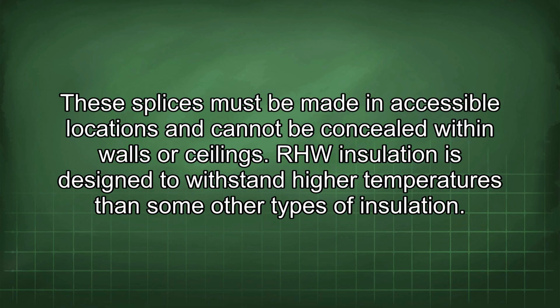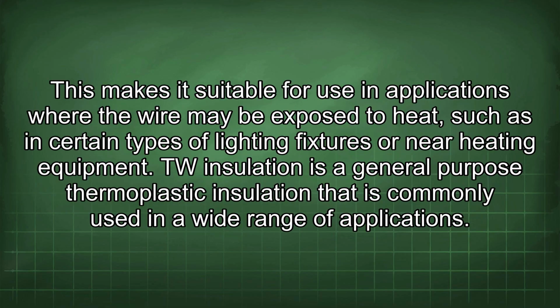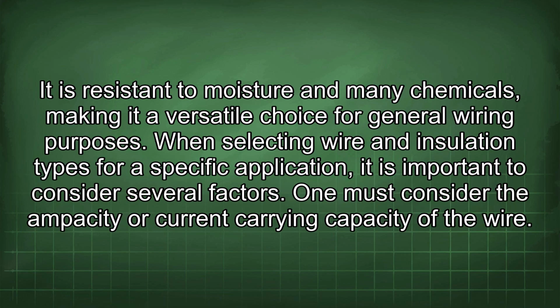RHW insulation is designed to withstand higher temperatures than some other types of insulation. This makes it suitable for use in applications where the wire may be exposed to heat, such as in certain types of lighting fixtures or near heating equipment. TW insulation is a general-purpose thermoplastic insulation that is commonly used in a wide range of applications. It is resistant to moisture and many chemicals, making it a versatile choice for general wiring purposes.